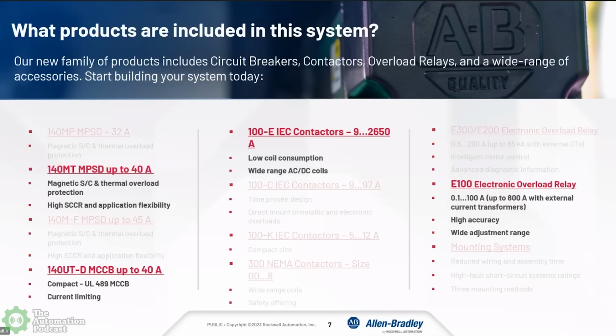Next up are the 100E contactors. The current range is 9 to 2650 amps, a really wide range there. One of the things we released on this is low coil consumption, so you actually command the contactor to open and close through an auxiliary. We offer a variety of AC and DC coils, but we actually have a low consumption coil that can be wired to the output of a PLC. So, Shawn, I'm not sure if you've ever had the experience of putting interposing relays in to activate a contactor, but we now have this where it can be done directly.